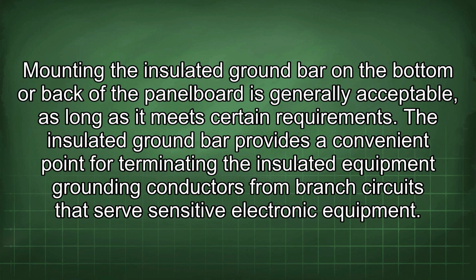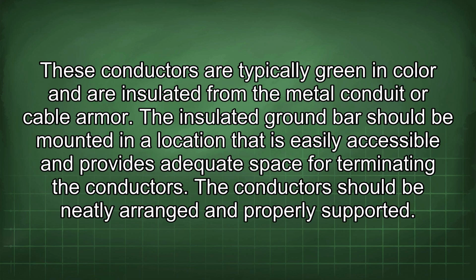The insulated ground bar provides a convenient point for terminating the insulated equipment grounding conductors from branch circuits that serve sensitive electronic equipment. These conductors are typically green in color and are insulated from the metal conduit or cable armor. The insulated ground bar should be mounted in a location that is easily accessible and provides adequate space for terminating the conductors. The conductors should be neatly arranged and properly supported.